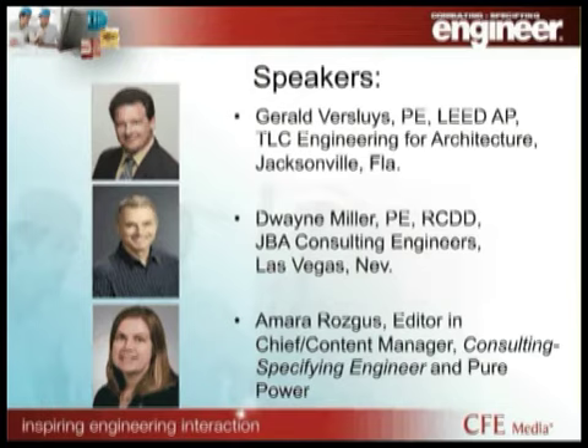Good, thank you. This next question for you, Dwayne, is about code. Wayne asks, does NFPA 110 apply to prime-rated diesel generators used as the primary power source system for multiple facilities? Well, I think that if you've got a primary source generator, then it wouldn't fall in the emergency and standby power systems category. So as a primary source of power, you've got a different set of codes that you would go with.